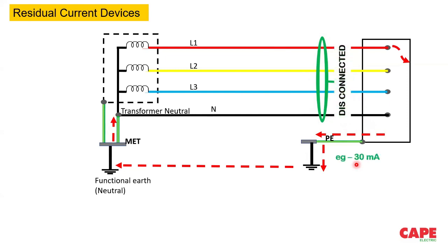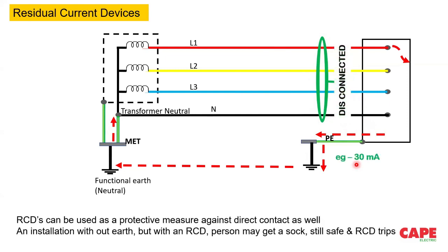Now, what you should understand in this particular case is, in an RCD, even if there is no earth wire, let us say by mistake there is no earth connection, you have an equipment and the protective earth conductor and the earth electrode itself is missing.